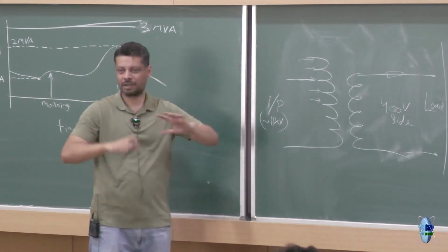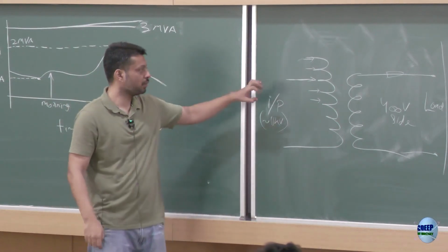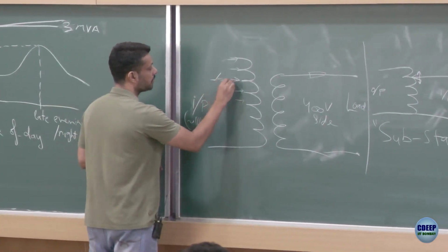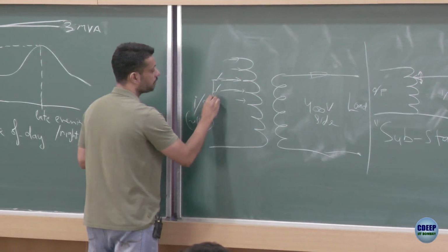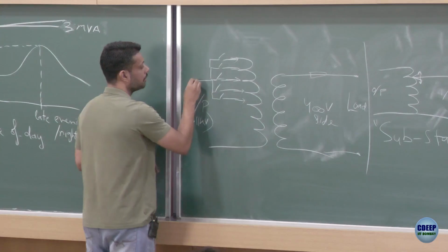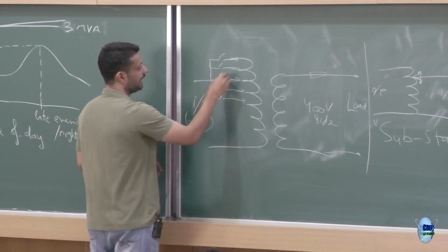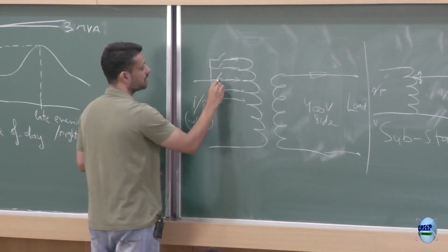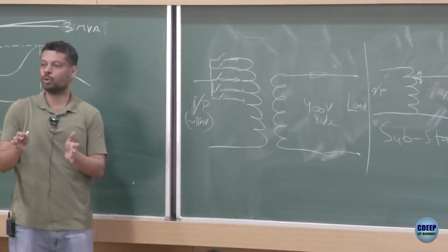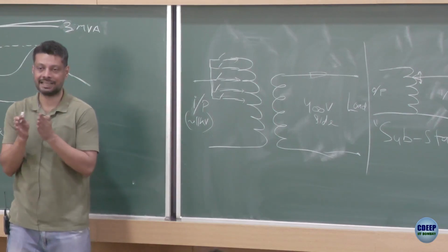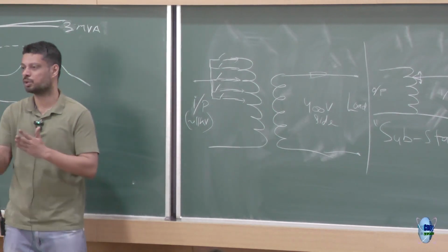So, you do not require very fine control anyway, so instead of doing that kind of mechanism, here you connect multiple switches, right, and then you can connect to this guy, you can connect to this guy, you can connect to this guy, you can connect to this guy, you can connect to this guy. So, it is doing something similar, of course in a limited range. You do not want to vary the voltage from 0 to 400 volt, you just want to do a fine adjustment of plus minus 10% or so.